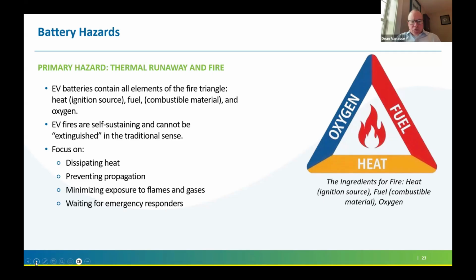The thermal runaway is something that, if it occurs, is self-sustaining. The batteries themselves have the fire triangle: a combustible source of energy, the material, they have oxygen, and they have heat as a result of internal failures.